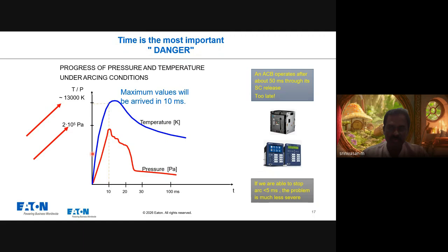Globally, if you look into the market, most manufacturers with an arc mitigation device have an arc protection relay. From the output of the arc protection relay, they give the signal to the breaker to clear the fault. For example, if you give the arc protection relay output to the ACB, the ACB takes 50 milliseconds to respond, whereas if you look at the graph, within 10 milliseconds the arc reaches the highest temperature. Our intention is to limit the arc flow in the network, so we need a device that responds in less than 5 milliseconds.